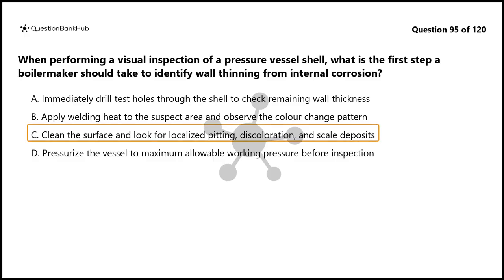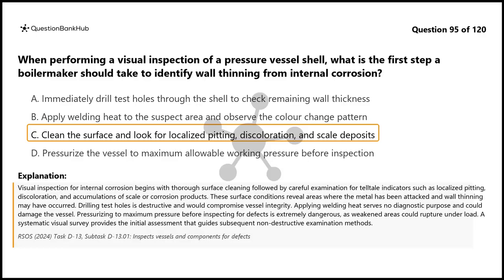The correct answer is C. Visual inspection for internal corrosion begins with thorough surface cleaning followed by careful examination for telltale indicators such as localized pitting, discoloration, and accumulations of scale or corrosion products. These surface conditions reveal areas where the metal has been attacked and wall thinning may have occurred.